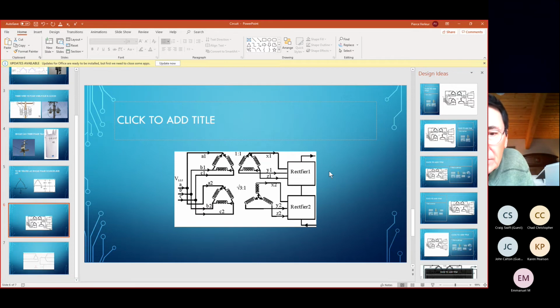This is old technology. This is passive filters. It is not compliant at all times. It is not compliant at all load levels. There is active technology out there, active front end drives, AFEs. Cost-wise, they're probably 20% more than the cost of an 18 pulse system, but you get compliance to IEEE 519 under all the critical situations, regardless of the variation of the power line, within reason.